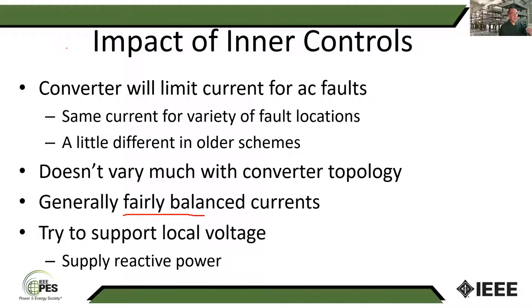So now with the 1547 language, they're really thinking in terms of, does this thing supply reactive power or does it consume reactive power? And so for supporting local voltage, it may be able to supply reactive power. And so the latest revision to IEEE 1547, 2 years ago, put in more ability for converters to actually do more active voltage control and participate in voltage management schemes for a distribution system.